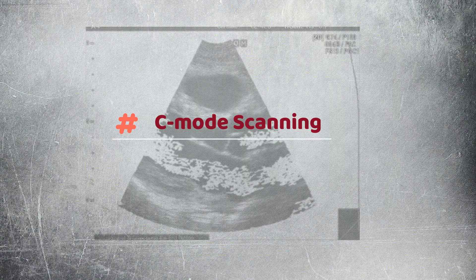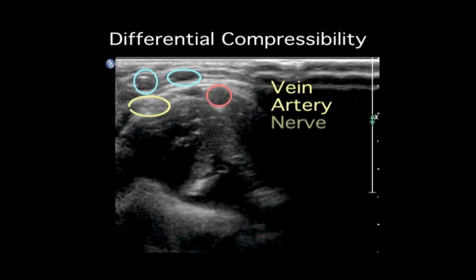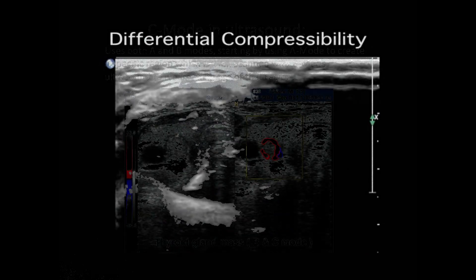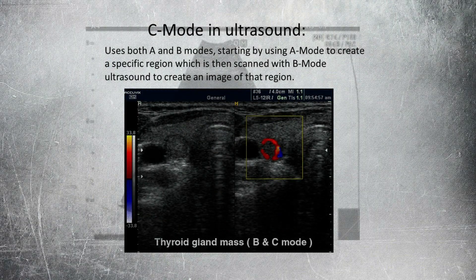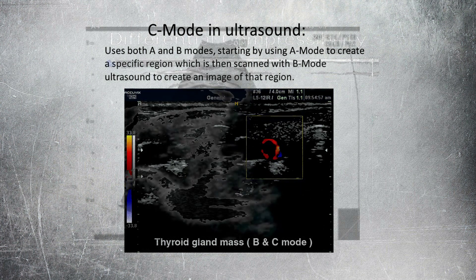A C Mode image is formed in a plane normal to a B Mode image. A gate that selects data from a specific depth from an A Mode line is used. Then the transducer is moved in the 2D plane to sample the entire region at this fixed depth.